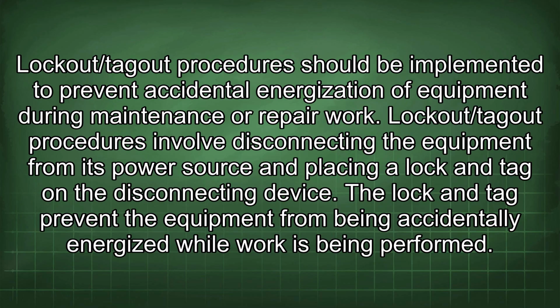Lockout/tagout procedures should be implemented to prevent accidental energization of equipment during maintenance or repair work. Lockout/tagout procedures involve disconnecting the equipment from its power source and placing a lock and tag on the disconnecting device. The lock and tag prevent the equipment from being accidentally energized while work is being performed.